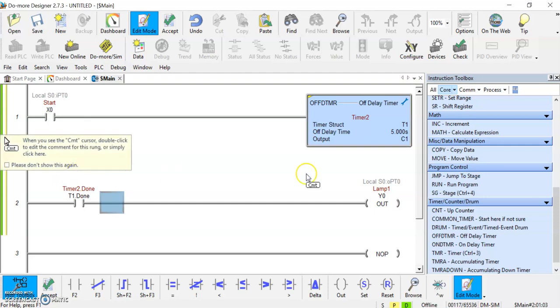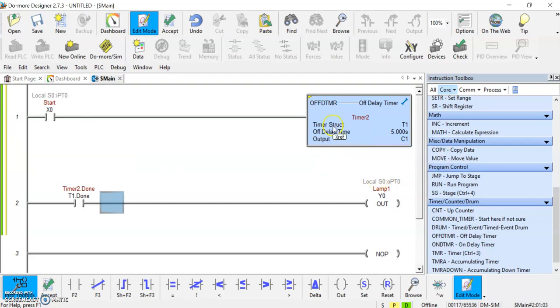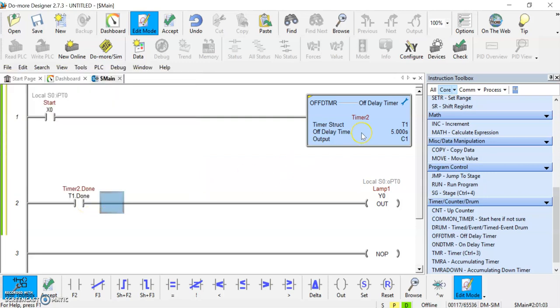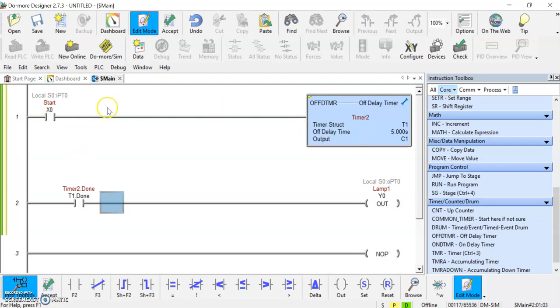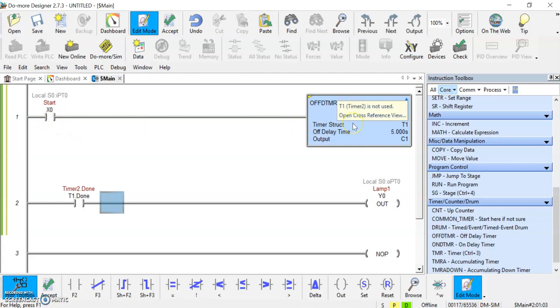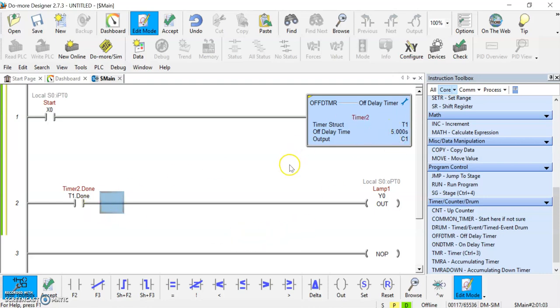So this program is going to look a bit different than our last one. This is an off delay timer. So what's going to end up happening is when this rung goes true, this will not be active until this timer goes off. And then it will be active. But it doesn't start timing, which is a little bit different. So when I did the last experiment here, this, when I activated this, it started timing right away. This isn't going to start timing until I actually remove this, until this rung goes false. And then when this rung goes false, then you'll see the timing. And it will start timing down instead of timing up. And then as soon as the time goes out, then this will go active. And my light will come on. So it's going to act about the same. It's just that this rung actually has to go false instead of true.